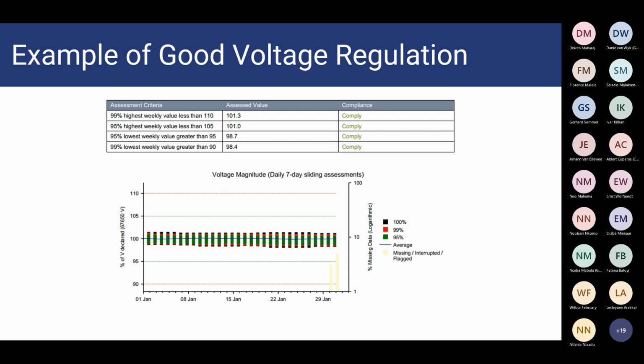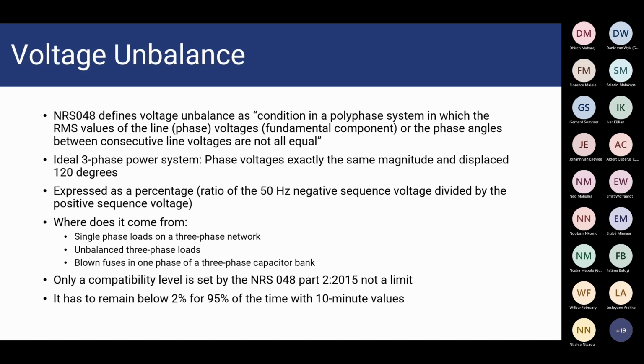Right, so that is how your voltage regulation is assessed and how you can compare your voltage regulation with the limits. Next, we have voltage unbalance. The NRS 048 defines voltage unbalance as the condition in a polyphase system in which the RMS values of the line or phase voltages of the fundamental component, or the phase angles between the consecutive line voltages, are not equal. So in an ideal three-phase power system, your phase voltages will be exactly the same magnitude, and they will be displaced 120 degrees out of phase. Now, voltage unbalance is a value expressed as a percentage of your negative sequence voltage divided by your positive sequence voltage. That is how voltage unbalance is calculated and defined.